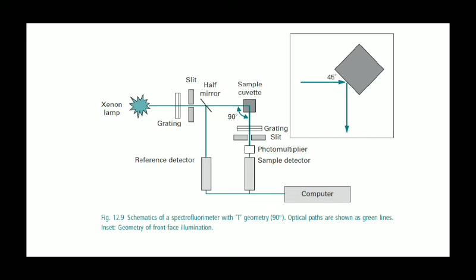Then wavelength selection. The simplest filter fluorimeters use fixed filters to isolate both the excitation and emission wavelengths. To isolate one particular wavelength from a source emitting a line spectrum, a pair of cutoff filters is all that is required. Like here you can see a pair of cutoff filters, two are required. Then recently, interference filters having a high transmission, approximately 40%, with a narrow range, that is 10 to 15 nanometers of wavelength, have become available, and it is possible to purchase filters with maximum transmission. So filters have a very important role in fluorescence spectroscopy, okay?